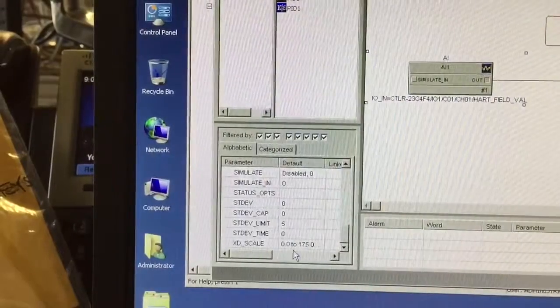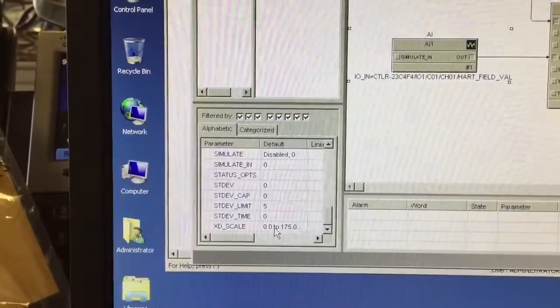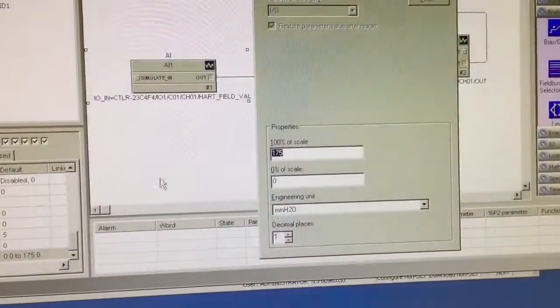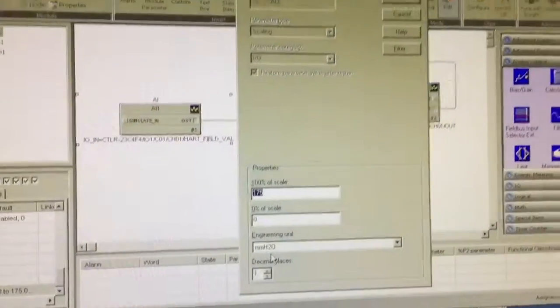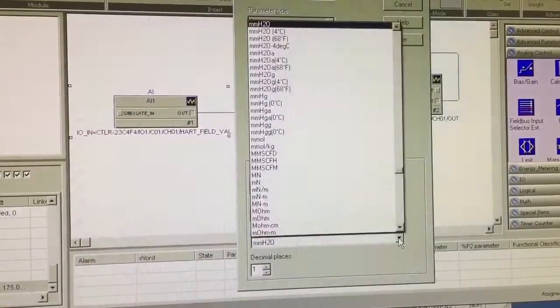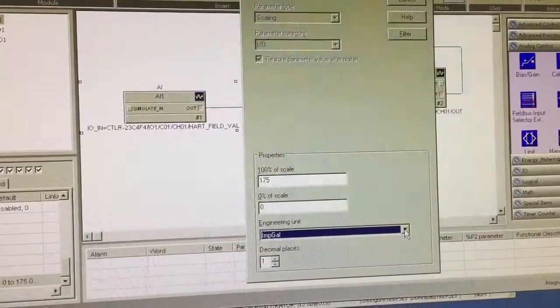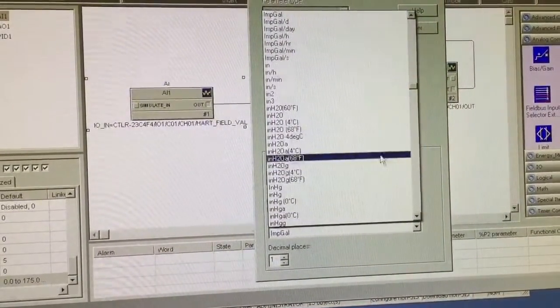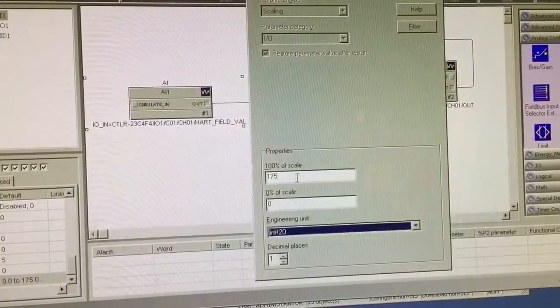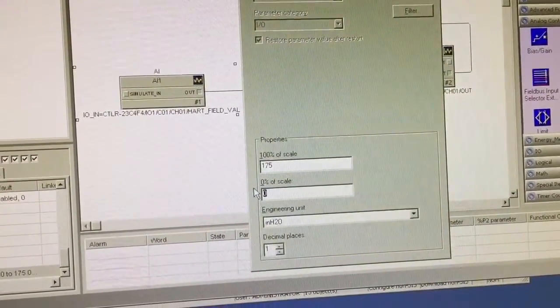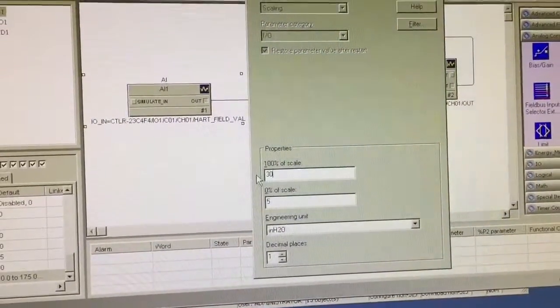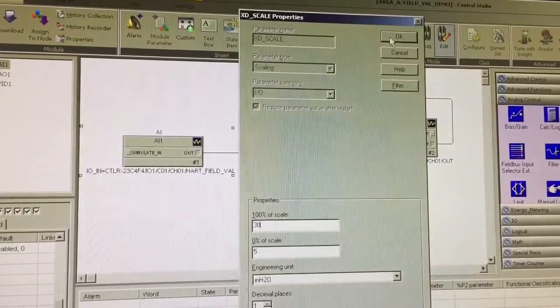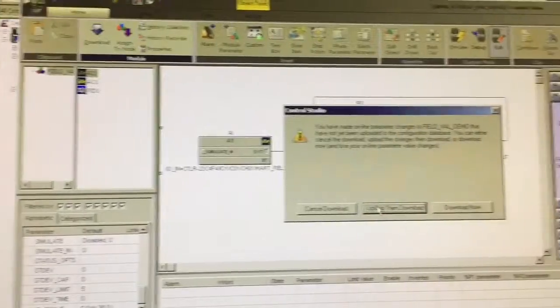If you scroll down and go to our XD scale, this here is the scale for the transmitter. If you double click here, you can see there's our zero to 175 millimeters H2O. So what I can do now, I can select this and change it to inches H2O. Let's rearrange this to 5 to 30 inches. We're going to click OK and now we're going to download this to our control system.